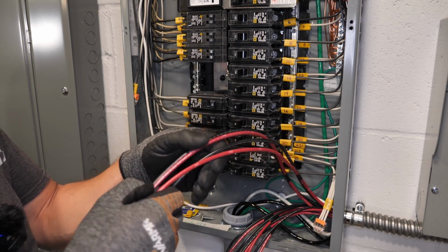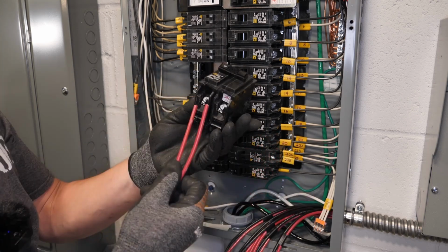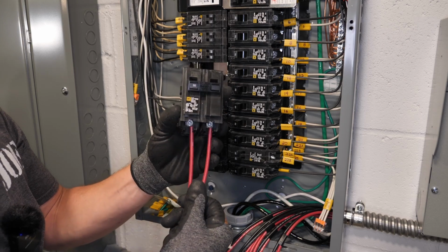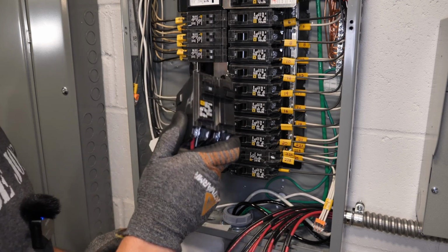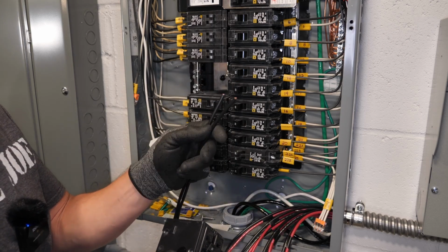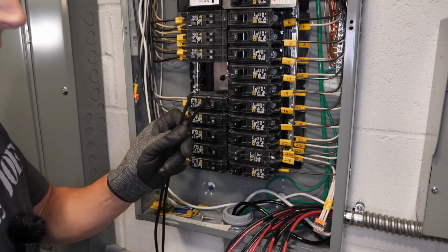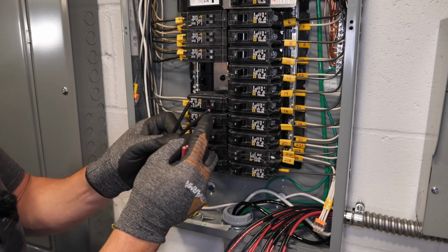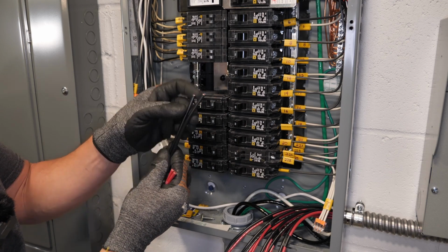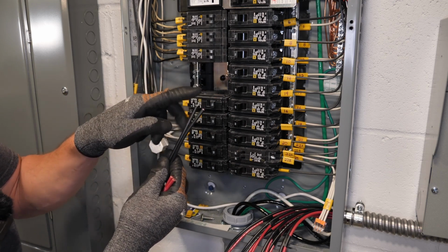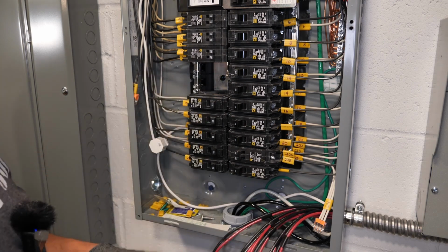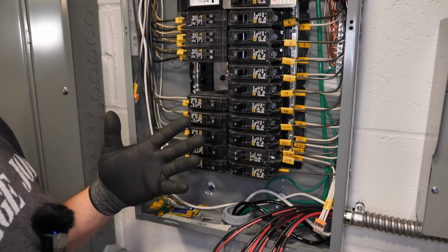We're going to grab the two red wires and wire those directly to the circuit breaker. Then the two black wires, A and B, we'll strip these back a little bit and wire nut them onto the well pump. That's how you wire a 240 volt circuit.